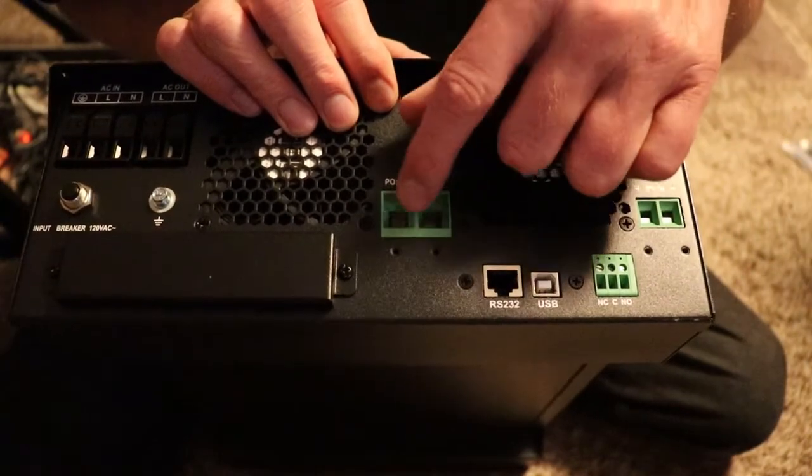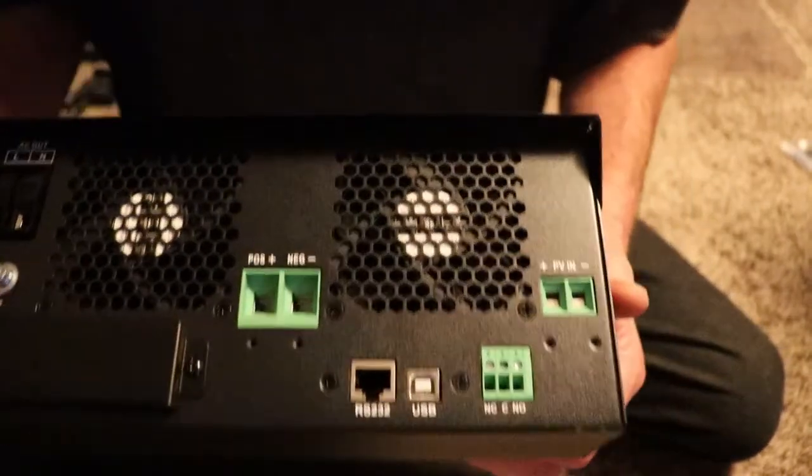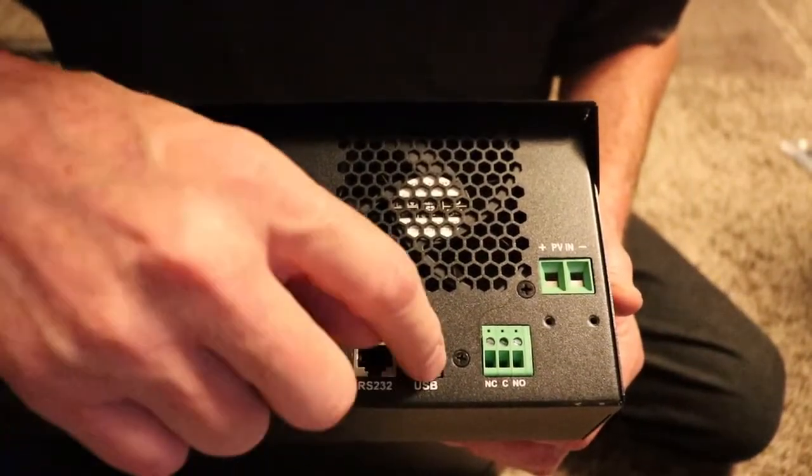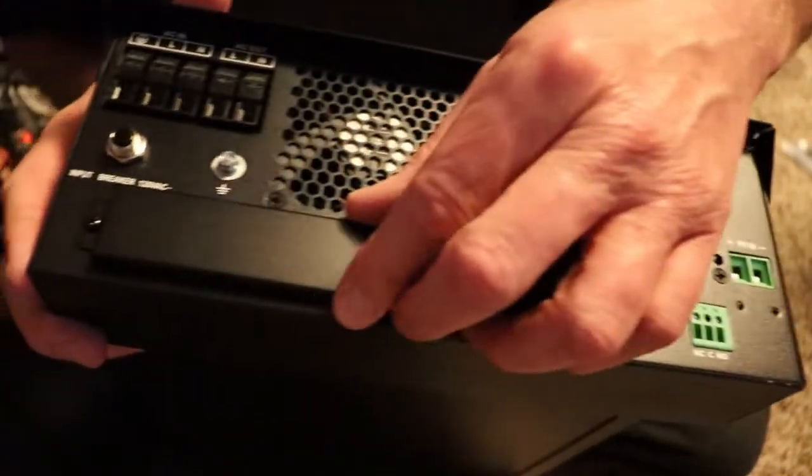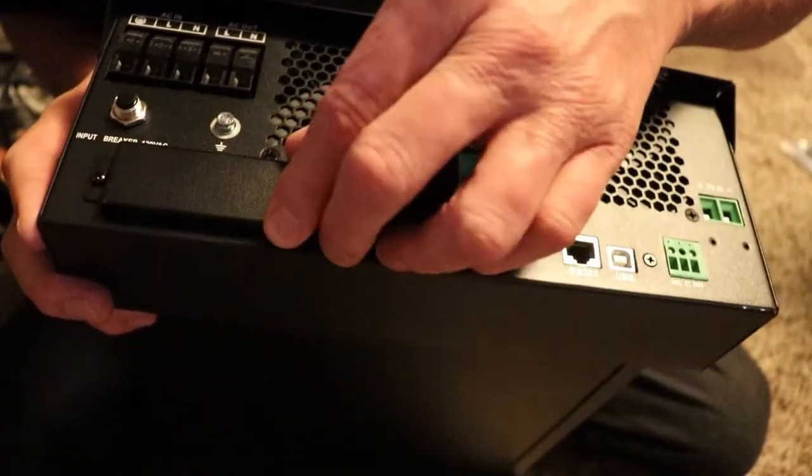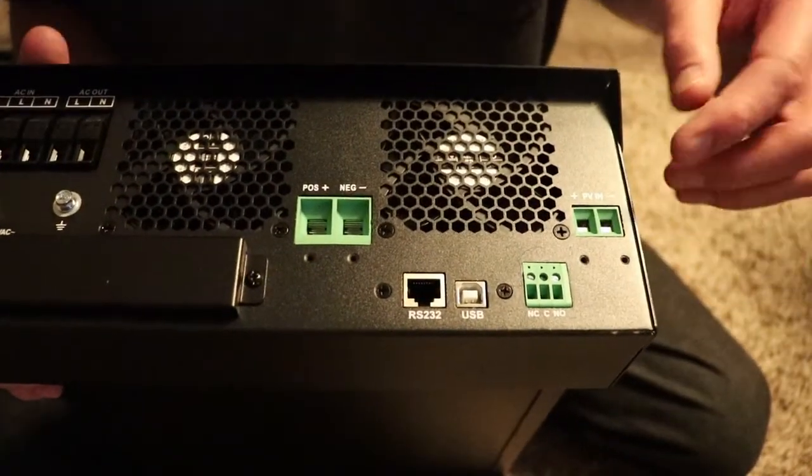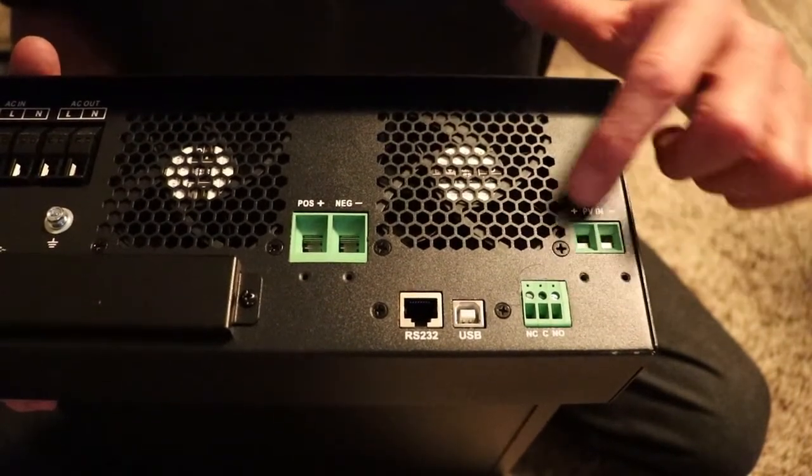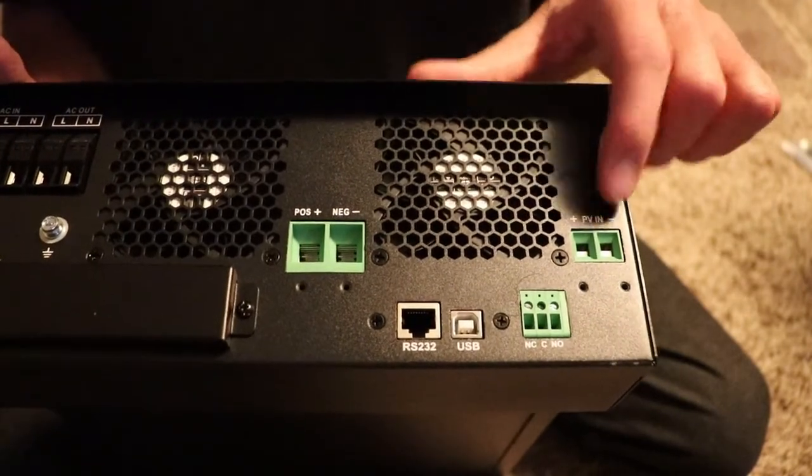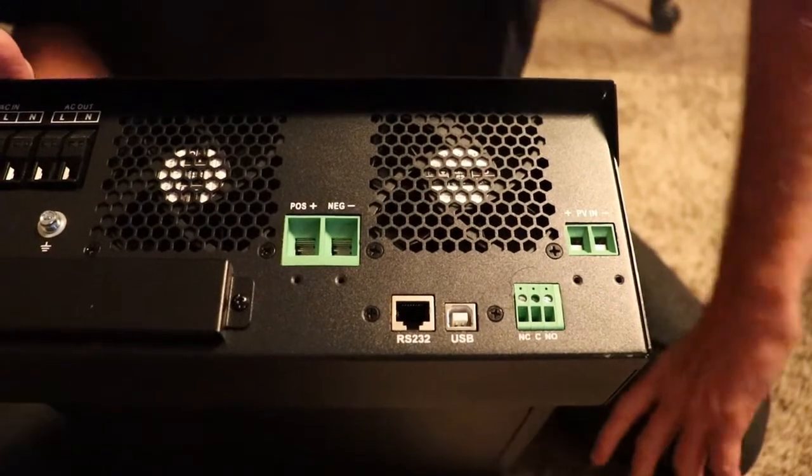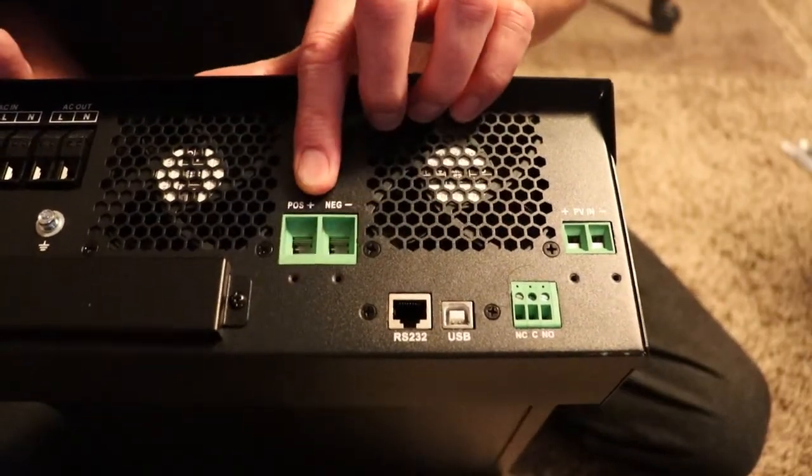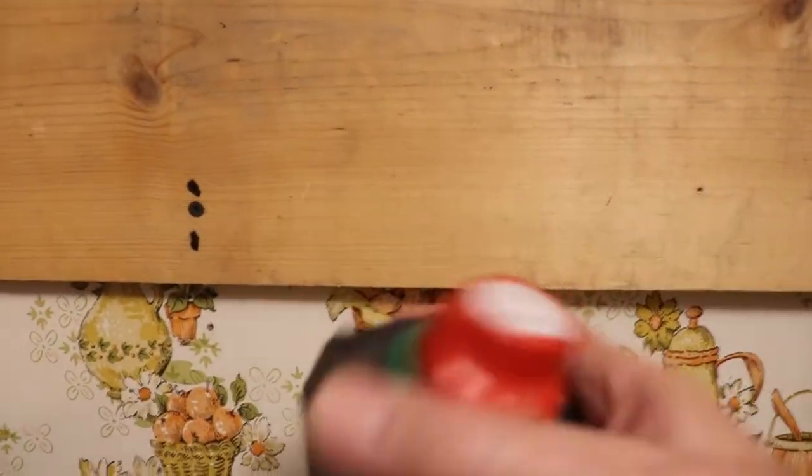The next part, this is some communication stuff right here. This is for USB, that's for a switch. This has fans here, you can see right here it has fans. This is where the fan covers are at right here. This is for other stuff that I'm not going to talk about right now. This is where your solar is going, the PV IN positive for the positive part of your solar system and the negative. That can hold up to like a 6 gauge wire. These are 4 gauge going to your batteries. These right here can be used at 12 to 48 volts DC. We're going to be running 24 volts.